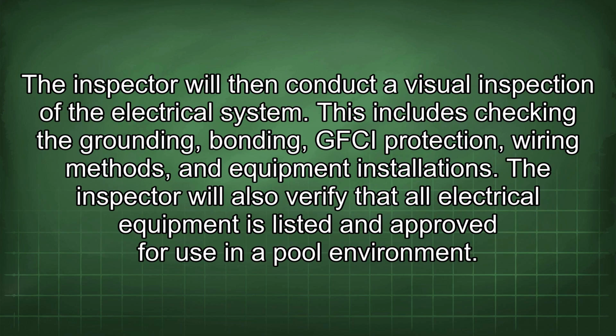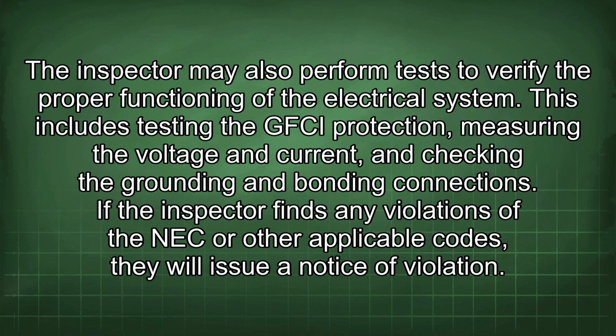The inspector will then conduct a visual inspection of the electrical system. This includes checking the grounding, bonding, GFCI protection, wiring methods, and equipment installations. The inspector will also verify that all electrical equipment is listed and approved for use in a pool environment. The inspector may also perform tests to verify the proper functioning of the electrical system. This includes testing the GFCI protection, measuring the voltage and current, and checking the grounding and bonding connections.